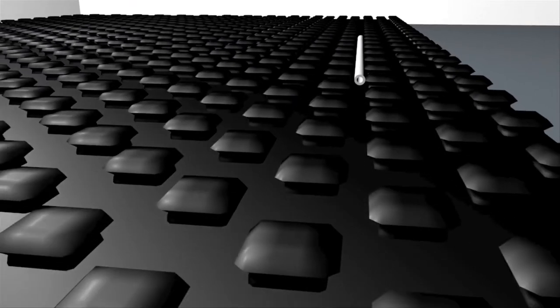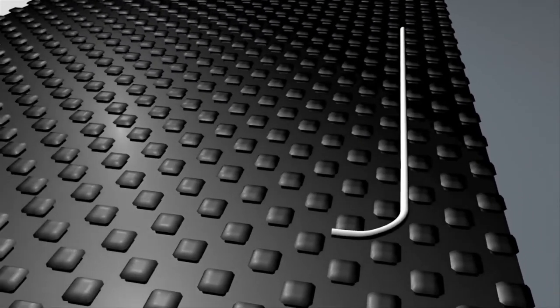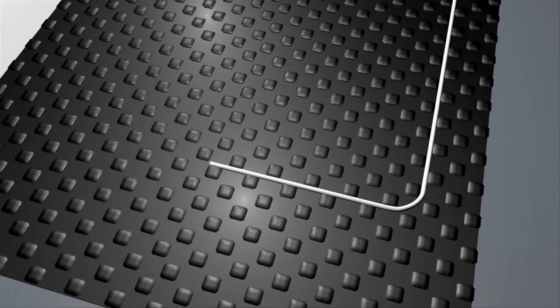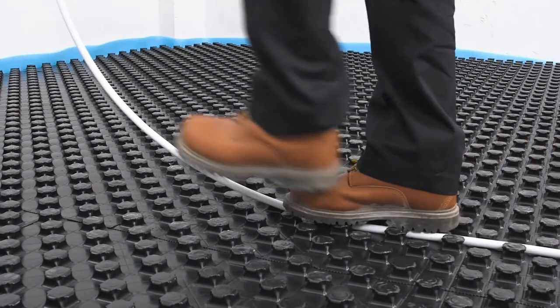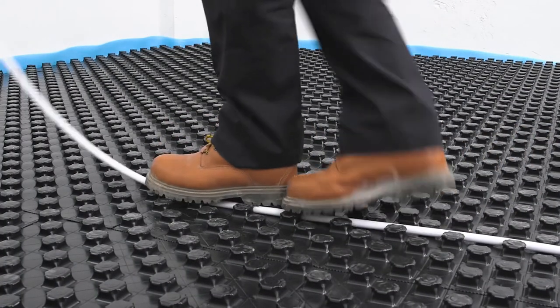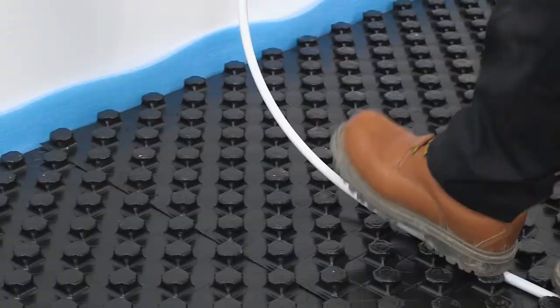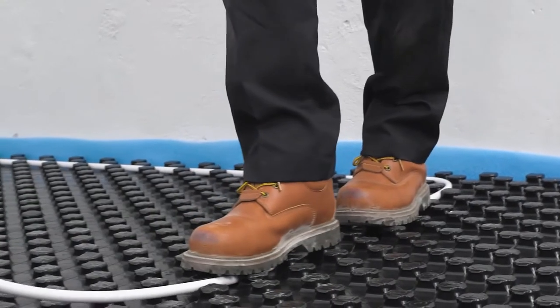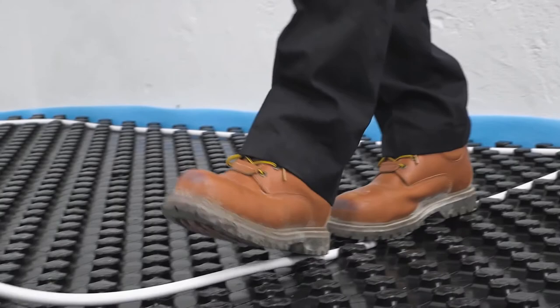It gives a secure pipe spacing system and allows the installer to perform an easy bending radius. Running the pipework between the castellations, install the pipework around the perimeter of the circuits to be laid. Work in a counter flow pattern and work from the outside towards the centre.